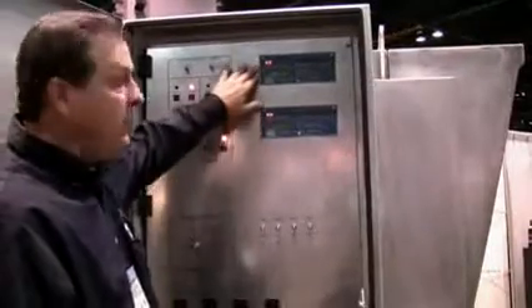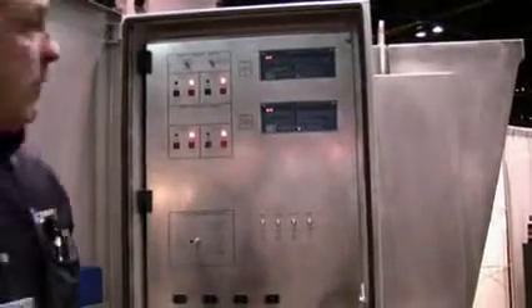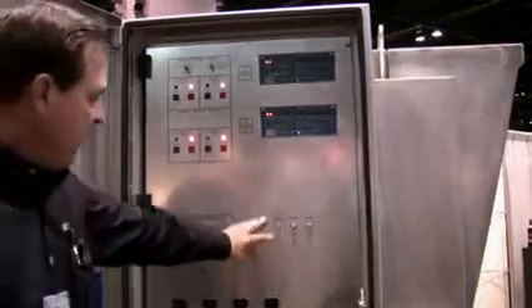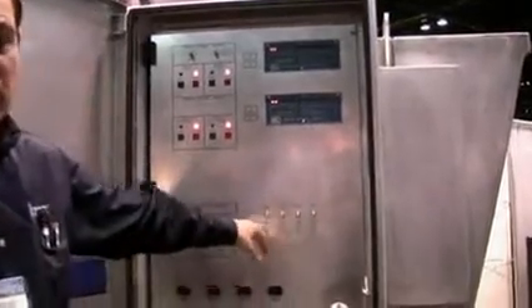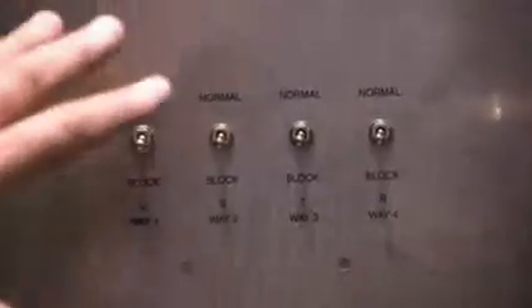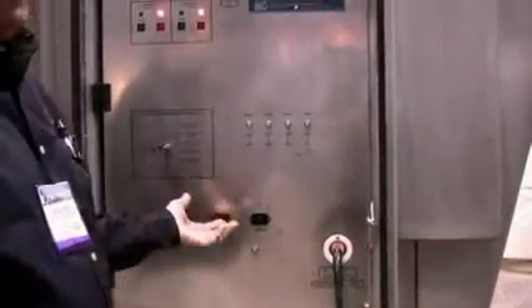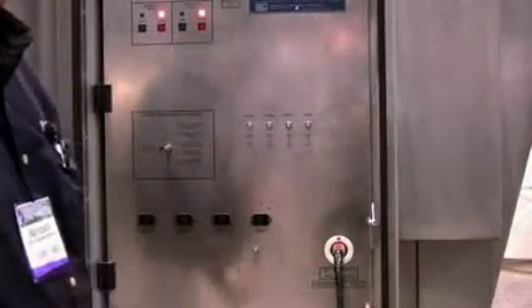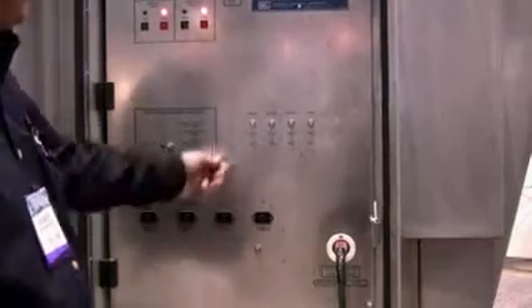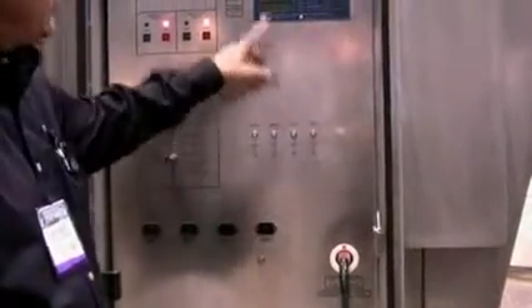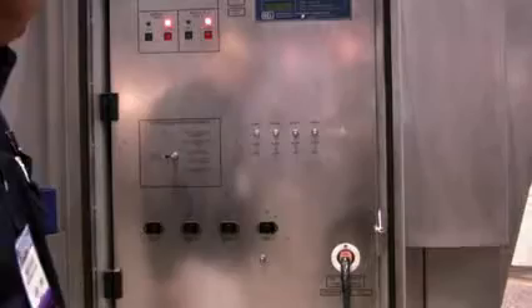This unit is using 50/51s for overcurrent protection. You'll notice we have toggle switches here which allow the relays to be locally blocked. Not only when they're in the block position do they block them locally, it also sends a signal back to SCADA to tell them that the overcurrent protection is blocked. It allows the line personnel, if there's a problem with an overcurrent relay and a breaker tripping, to actually flip the switch and block the tripping of the relays.